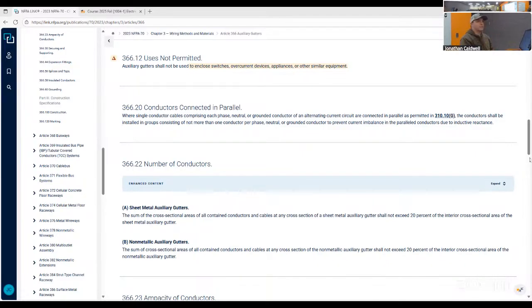You want to make sure they're still all together. Ideally, they'd be twisted together, but most of us don't deal with twisted wire. So you at least group them together. So you'd have your A, B, C, and your neutral for that one parallel. You group that together. And the reason for that, that keeps that magnetic force together from the phase shift and all that, the AC theory. That keeps it all together so it doesn't jump to another with the same parallel run. So that's why you keep that all together.